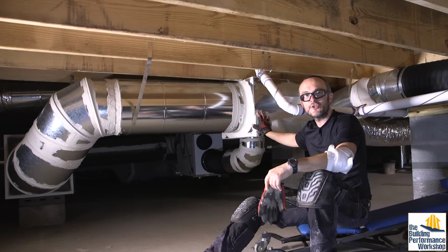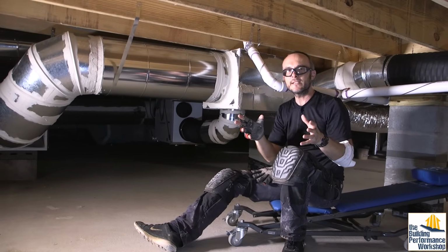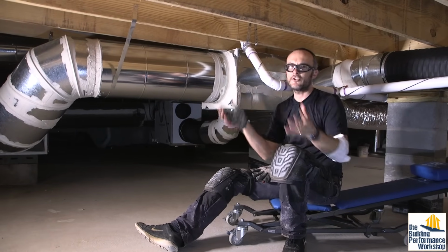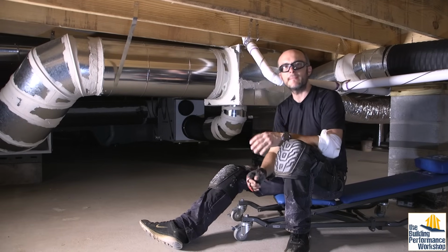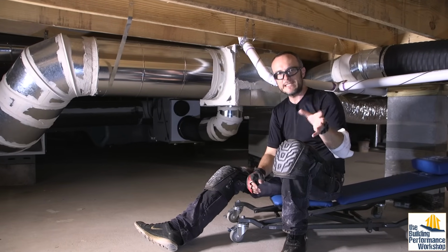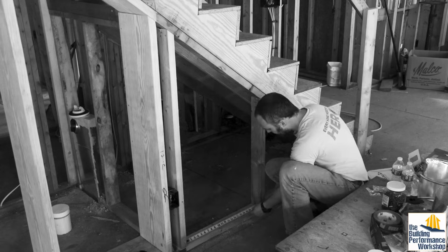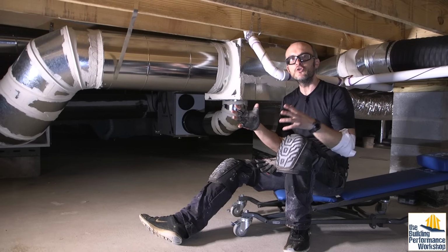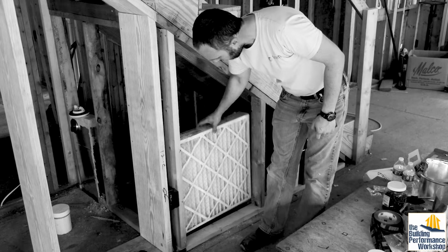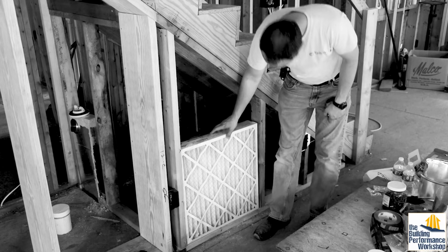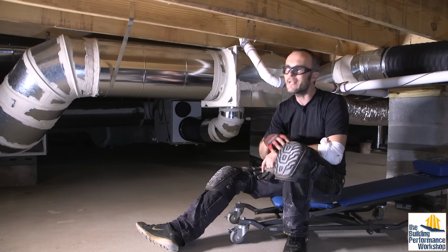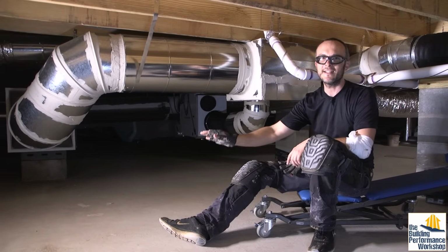This box, by the way, I was pretty proud. We built this. I showed a little bit of that in a past video, but they don't make plenums that are universal sizes. For some reason, all the manufacturers just make ones that are for their specific brand. And so you just gotta buy one that's in the range. I needed a 2 foot by 2 foot by 2 foot cube to be able to put a 2 by 2 filter that's a 2-inch deep filter on. And of course, getting that 2-inch deep filter, like all the things that we're doing on this house, is pretty much non-standard for the entire HVAC industry.